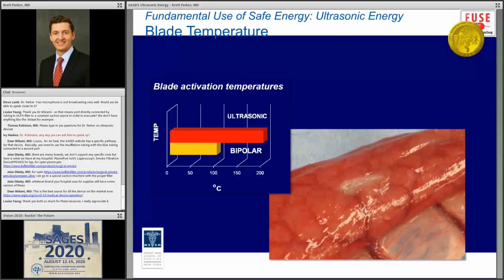And that active blade, the oscillating blade, can retain heat and it stays hot after its activation. So if the surgeon is distracted or inadvertently touches this hot blade, which is not being actively used, it can lead to unintentional thermal injury, as you can see on this piece of bowel here. It's definitely something that has a learning curve, should constantly be remembered and constantly avoided when beginning to use this device.